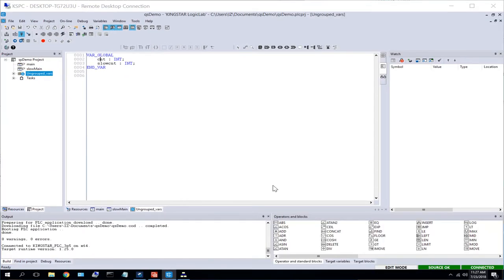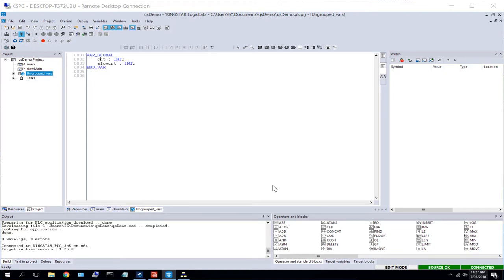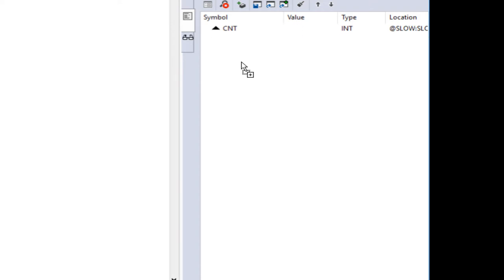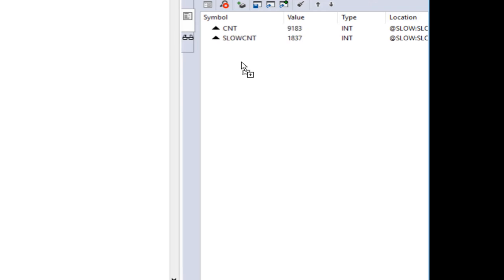OK, so let's actually verify that we are executing on the PLC target. Now the way we're going to do that is via the last thing that I want to talk to you about today, and that's the watch window. It's very easy to just grab any type of variable you want, whether it be IO or a global variable, etc., and just drag and drop it into the watch window. So we're going to do that right now by going to our global variable list and grabbing both our count variables. And we're going to just drag and drop them right in there, and you can see they're already spinning because our PLC is running. And at any given time, we should be able to stop this and see that slowCNT is actually about five times slower or smaller in terms of its value than count, and that's because it has a five times slower cycle time.